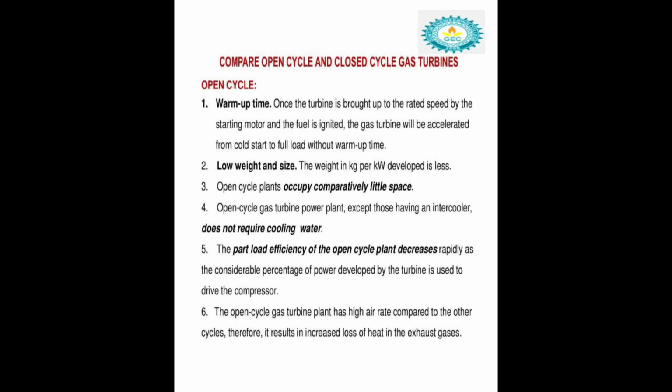Now the comparison between open cycle and closed cycle gas turbines. First, the open cycle gas turbine warm up timing. Once the turbine is brought up to the rated speed by the starting motor and the fuel is ignited, the gas turbine will accelerate from cold start to full load without warm up time. Another advantage is low weight and size. An open cycle plant occupies less space as compared to the closed cycle gas turbine.